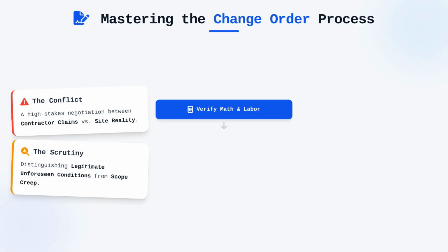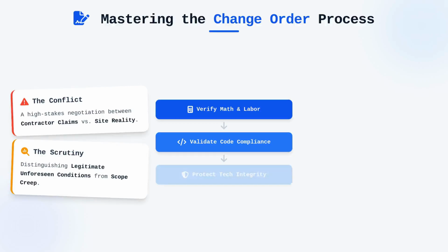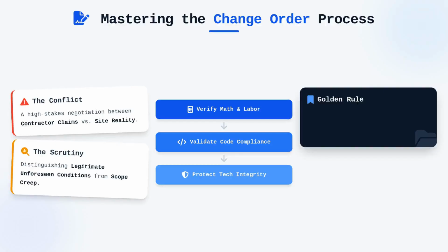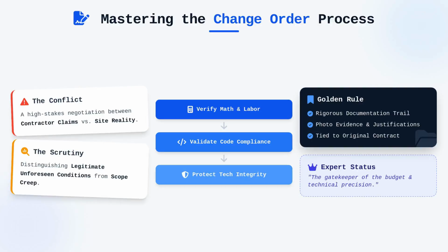If the request stems from an owner-driven requirement, you must ensure that the change does not violate existing code requirements or compromise the performance metrics of the structured cabling system you have meticulously designed. My recommendation is to always maintain a rigorous documentation trail, including photographs, impact assessments, and justifications that are tied directly to the original contract. By positioning yourself as a gatekeeper of the budget, you protect the client's interests and maintain the project's technical integrity against pressure to accept shoddy work or unjustified markups. This dual focus on technical precision and fiscal oversight is what separates a proficient designer from an expert consultant who can manage the pressures of a complex construction site.